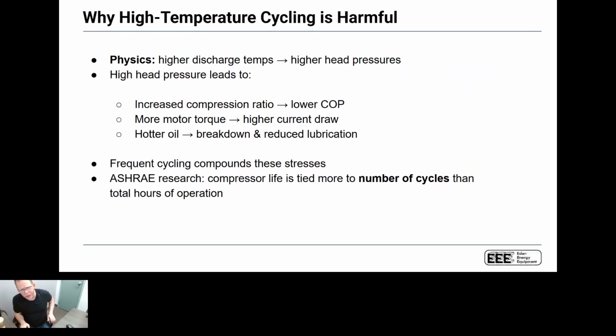So the other thing to certainly keep in mind is that we want to be very, very careful about high temperature cycling. If we have a unit that's running for domestic hot water applications, so you take an HPX5, for example, that can get up to 140 degrees, we don't want to be driving it up to 140 degrees, not having anywhere for that energy to go, and then shutting it off, driving it up, shutting it off. There's actually a really good ASHRAE study that shows this is a really good way to kill a compressor. As somebody who's dealt with hydronic heat pumps for over 20 years, I don't need ASHRAE's research to tell me this is a really, really good way to kill a compressor.